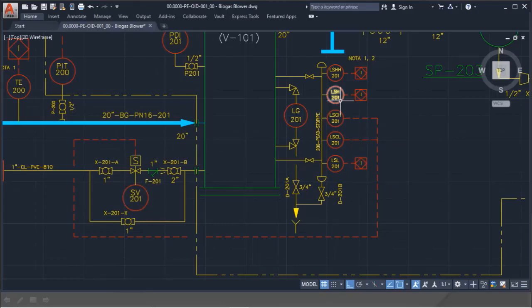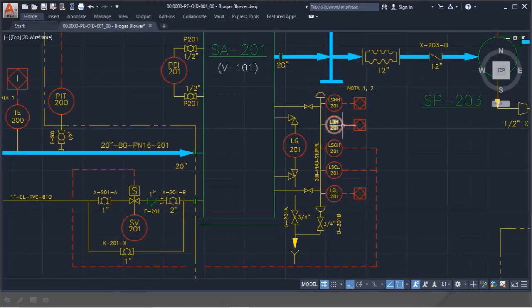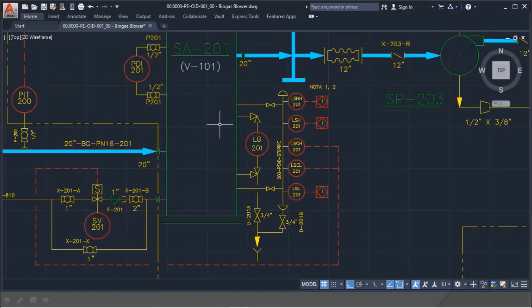We also have another two switches here. One is related only to alarm. When the liquid reaches this level, the control room will have an alarm to know that the separator vessel is filling. And we have a shutdown related to high level. So if we reach this LSHH, we have a shutdown of the plant to prevent liquid going to the blowers.